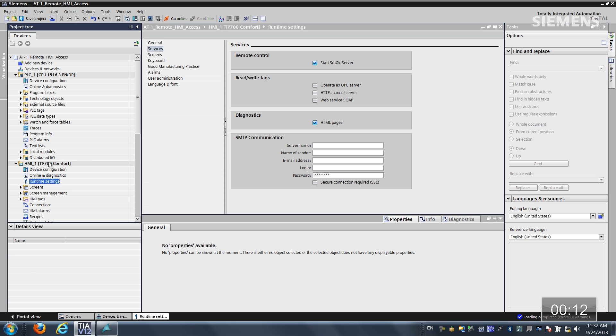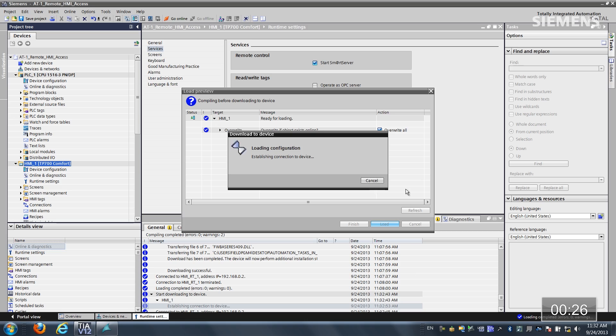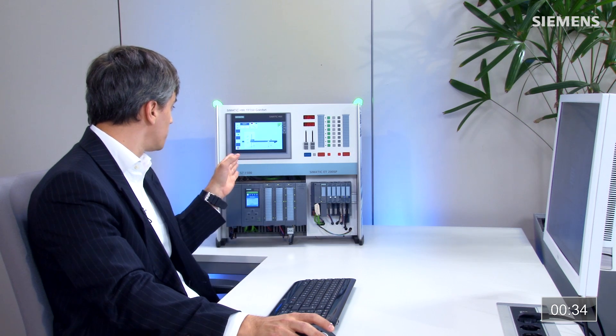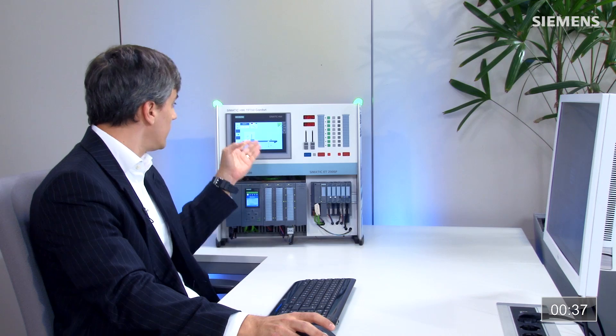Now I'll give focus to the HMI and click on the Download button. It's going to compile the fact that I've added a web server into the current HMI. Once compilation is finished, I can click on Overwrite All and then Load. It's going to load this new configuration down to our HMI panel. Once done, it appears finished — we've made the new connection and now have a web server enabled on this HMI panel.